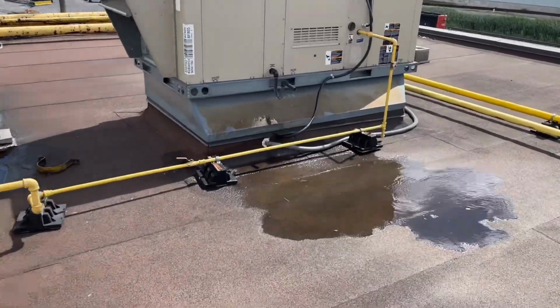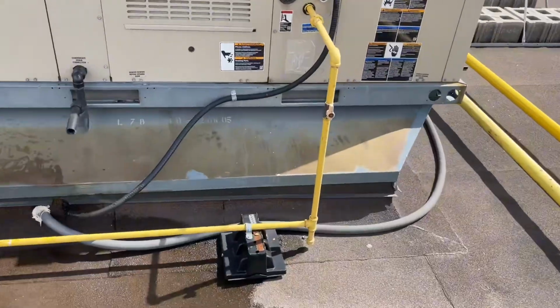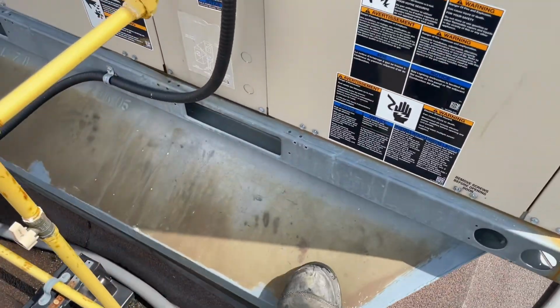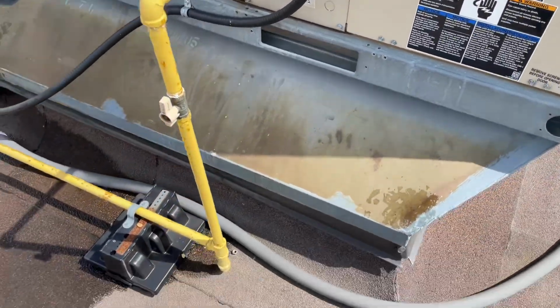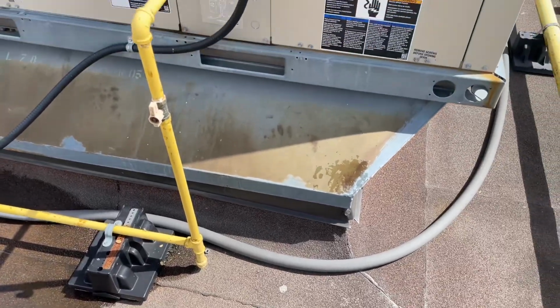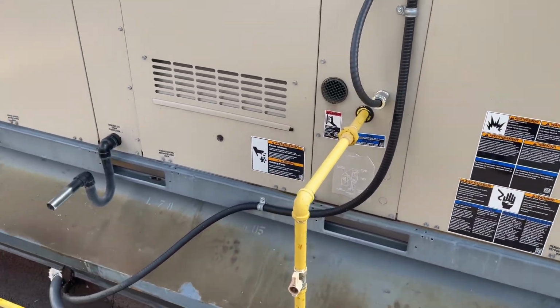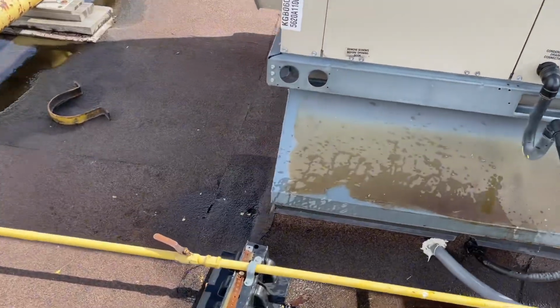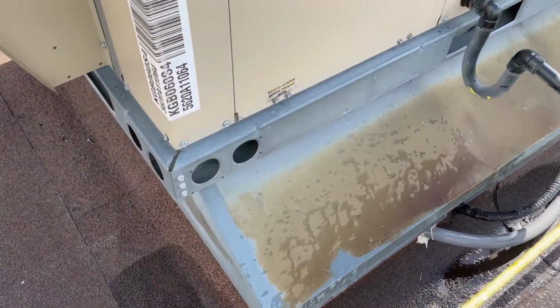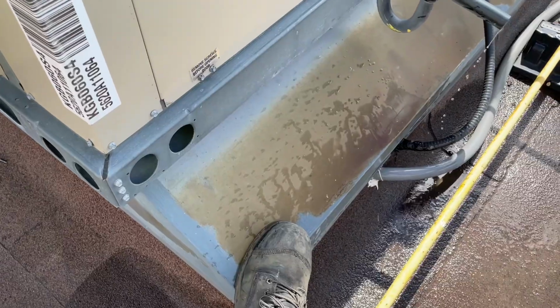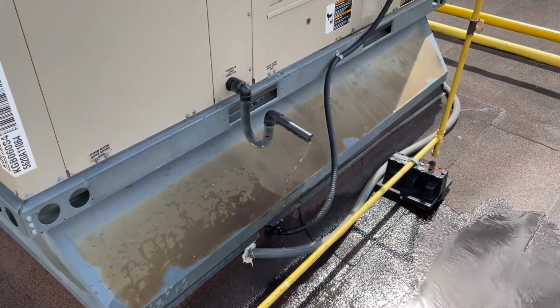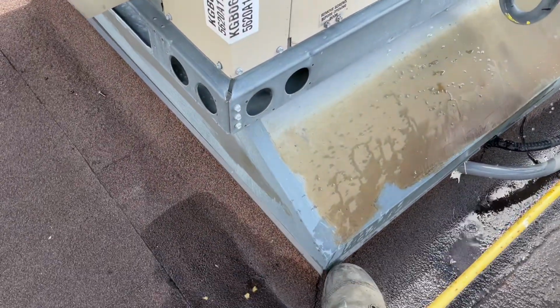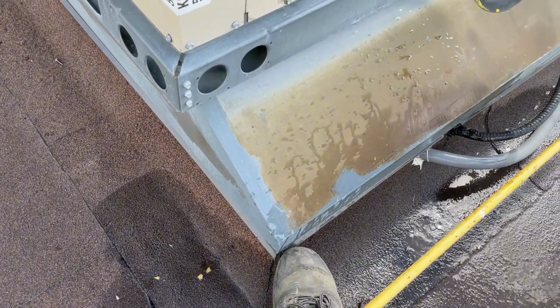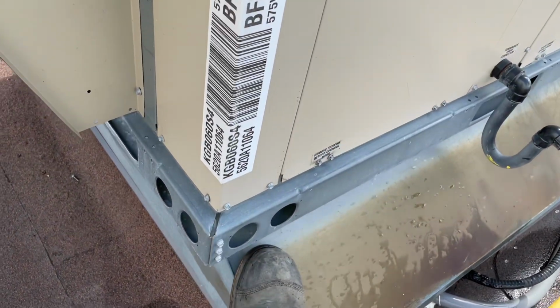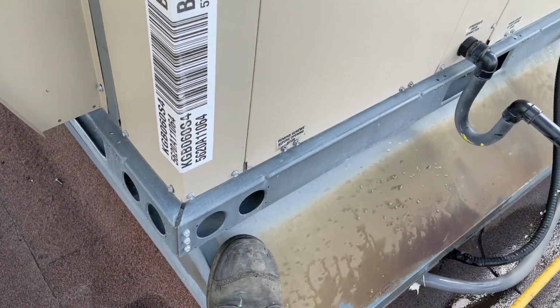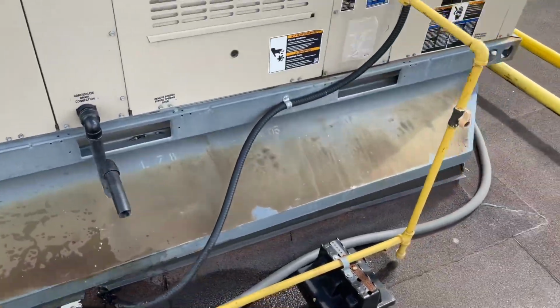And to end things off here, guys, I'm gonna show you the curb adapter now. This is a different unit, but you see this right here? That fits on our original roof curb and adapts to our rooftop size. So be careful. You guys might have to measure both of these if you're replacing a new rooftop and it has a curb adapter. Take both measurements to be safe. One at the bottom here, where that fits on our existing roof built-in flashing, and then our adapter size here, because you never know, you might be able to get a unit that will fit this curb adapter. Maybe you'll have to change both.